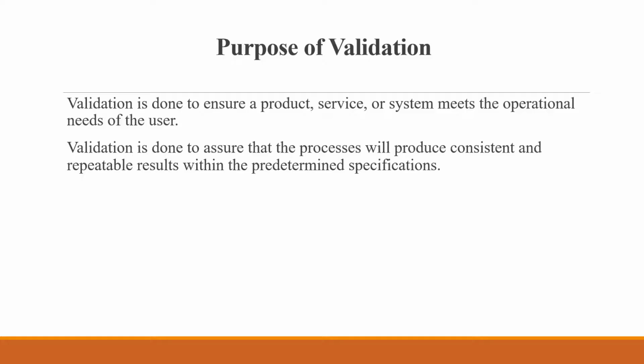Now how will it pass validation? If it reached the maximum capacity of 100, it should maintain between 2 to 6 degrees. If the temperature rises more than 6 degrees, it failed validation, because its recommendation is 100. Try putting in 101, for example. Will it reach 6 or 7 degrees? If it maintains within the 2 to 6 degree range, then it passed validation.